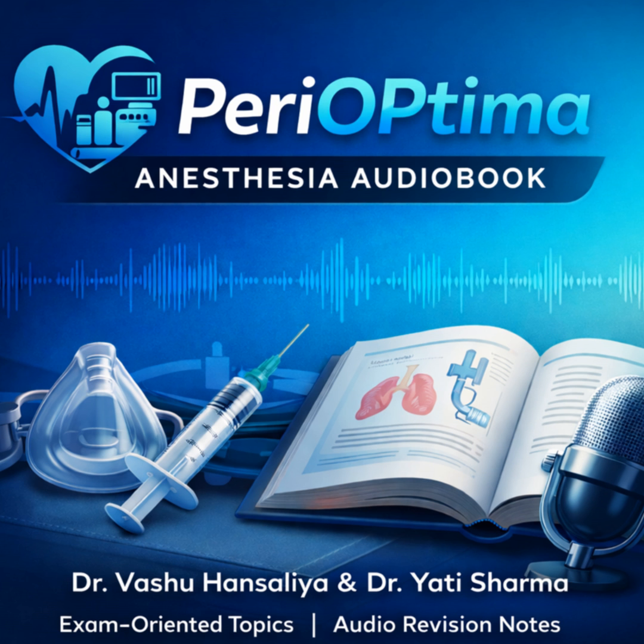First, the common gas outlet, or CGO. This is really just the terminal point of the machine's internal piping. It's where the fresh gas flow, the mixture of oxygen, other gases, and vapor, exits the machine to connect to the breathing circuit. It has a standard 22mm outer diameter and a 15mm inner diameter connector.